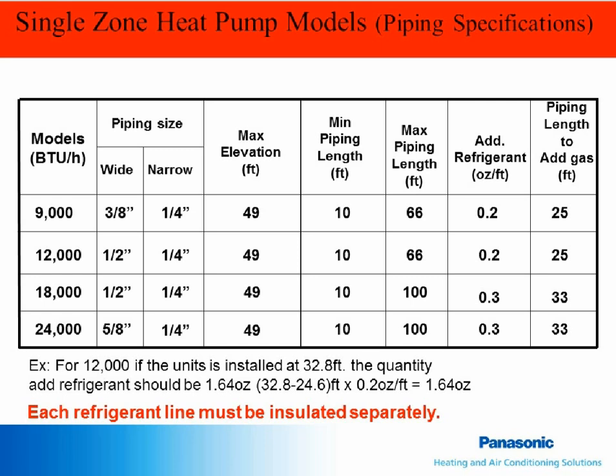All refrigerant lines must be insulated separately. In this example, a 12,000 BTU model requires a half-inch wide, or suction, line and a quarter-inch narrow, or discharge, line. The maximum elevation difference between the indoor and outdoor unit is 49 feet. The minimum piping length is 10 feet, and the maximum length is 66 feet. The unit comes charged for 25 feet of line set, and anything over that at 0.2 ounces per foot.